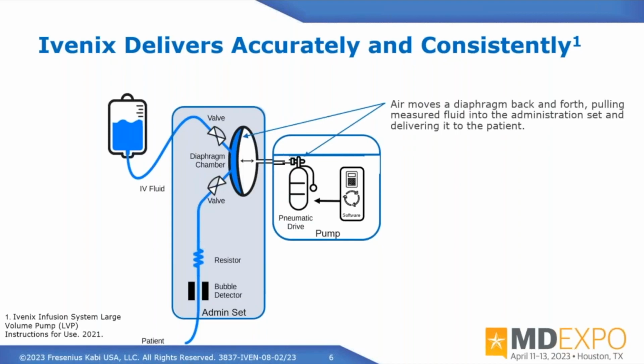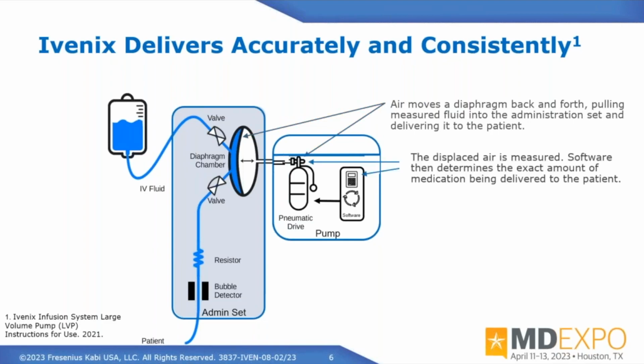Air moves the diaphragm back and forth. It's measured. We know the calibration of the administration set. We're able to measure the air through that pneumatic system. Measuring air is equivalent to measuring the fluid because of Boyle's law, consistent pressure in a closed system. Software determines exactly what we should push for the rate and the pressure in the system.